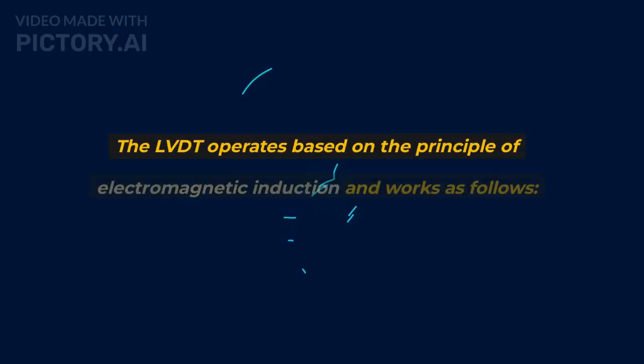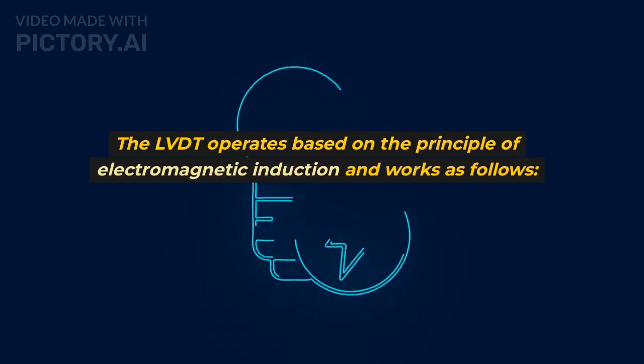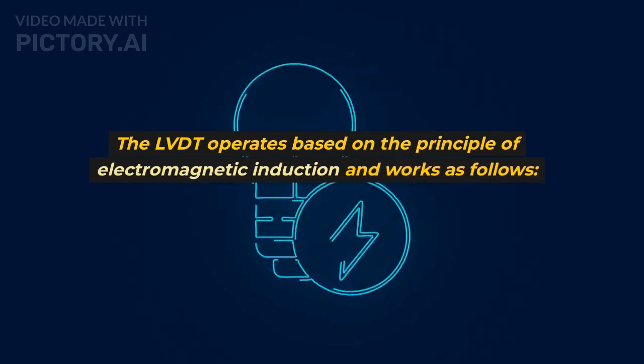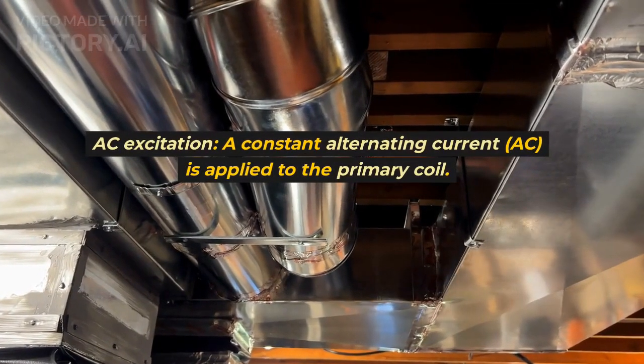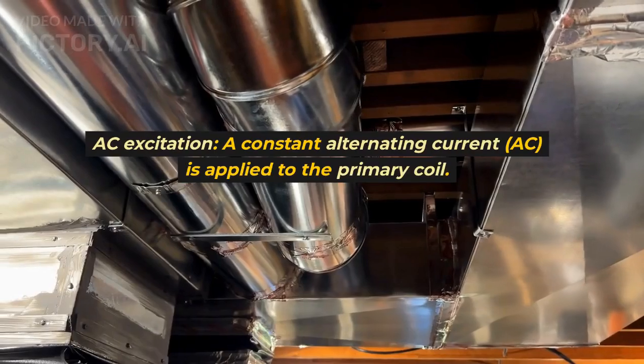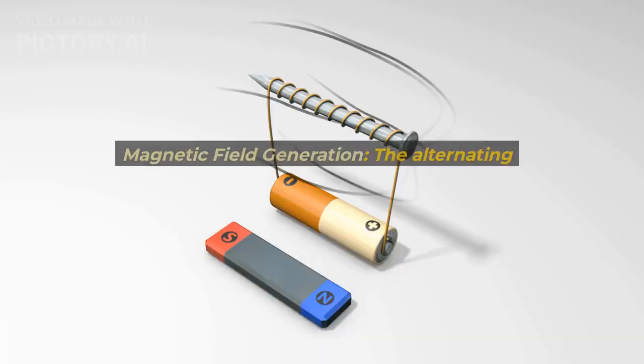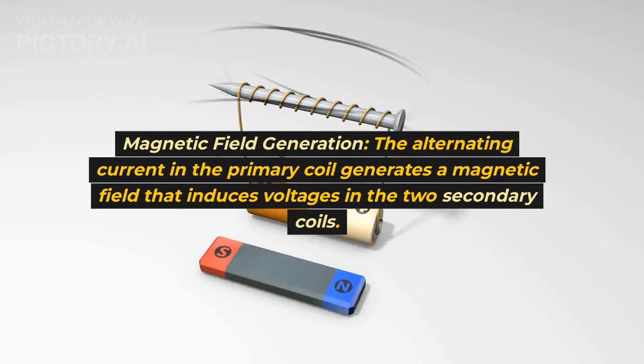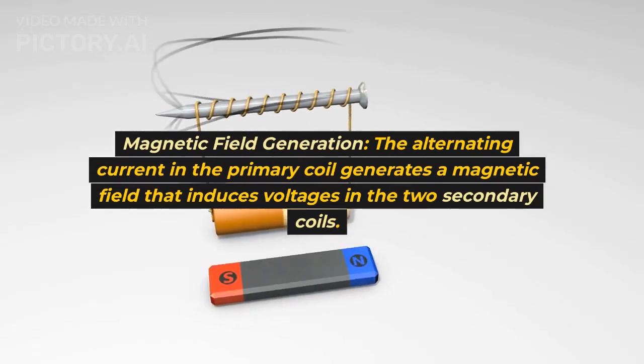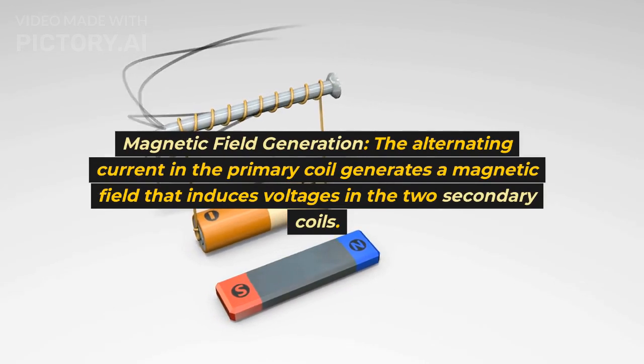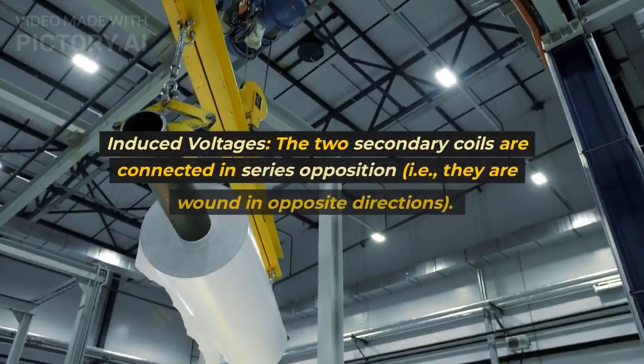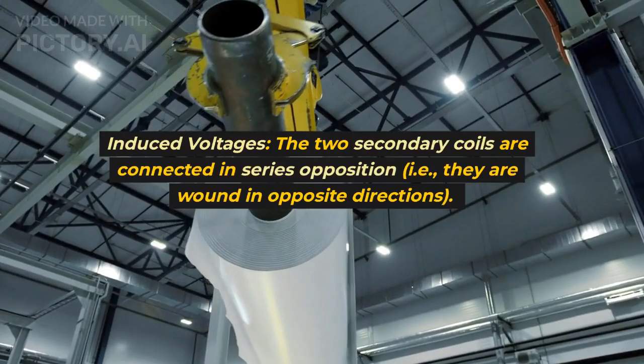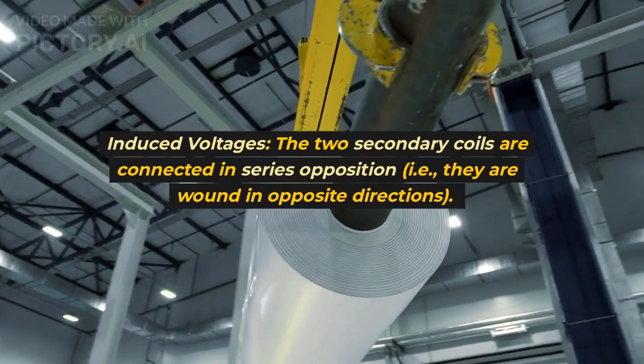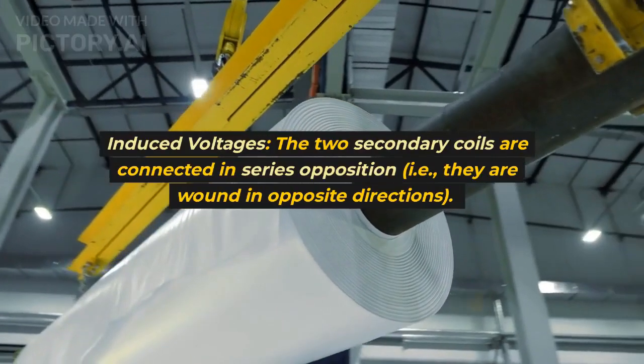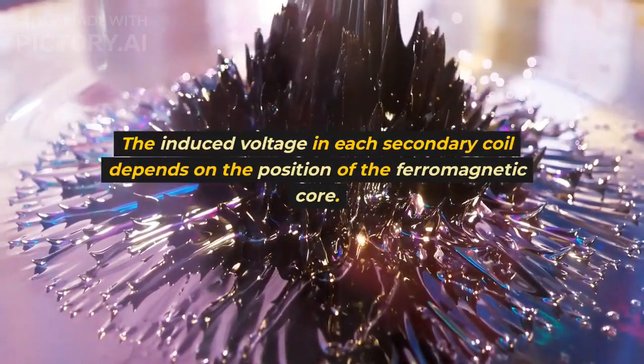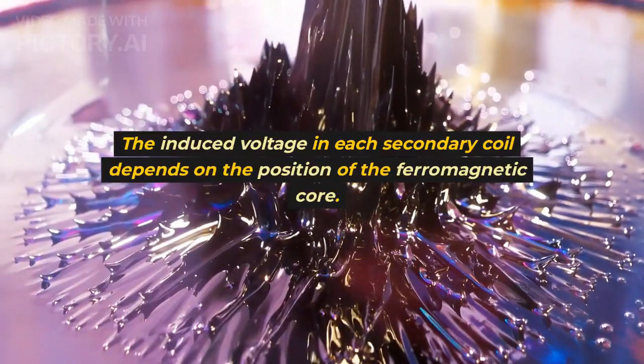Working principle. The LVDT operates based on the principle of electromagnetic induction and works as follows. AC excitation: a constant alternating current, AC, is applied to the primary coil. Magnetic field generation: the alternating current in the primary coil generates a magnetic field that induces voltages in the two secondary coils. Induced voltages: the two secondary coils are connected in series opposition, i.e., they are wound in opposite directions. The induced voltage in each secondary coil depends on the position of the ferromagnetic core.